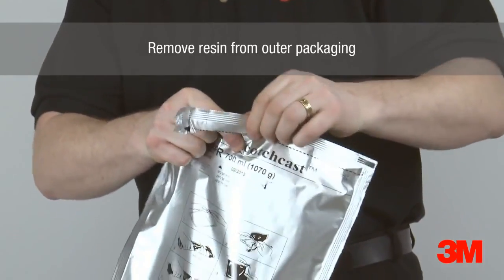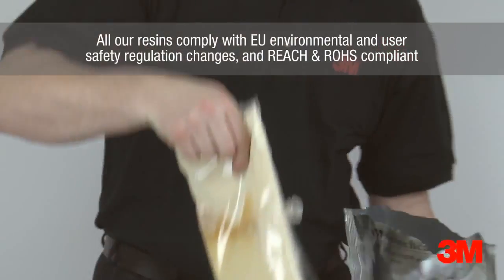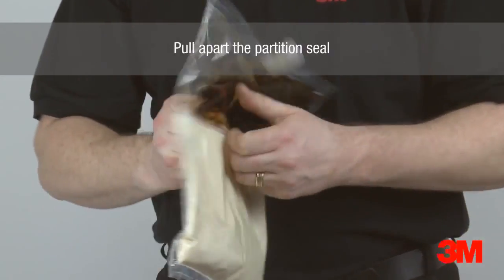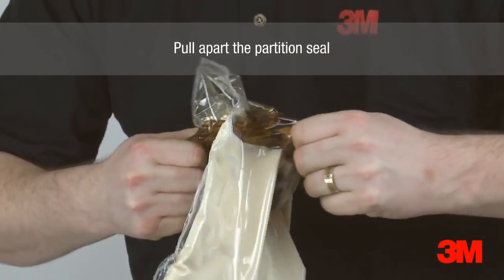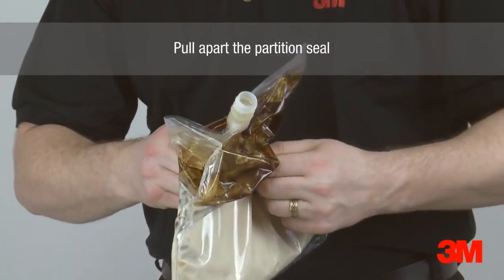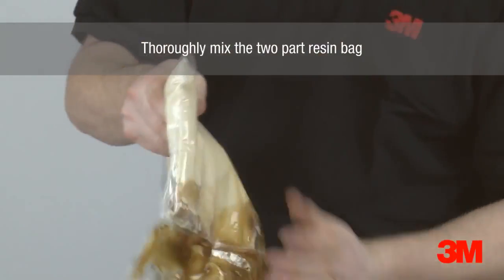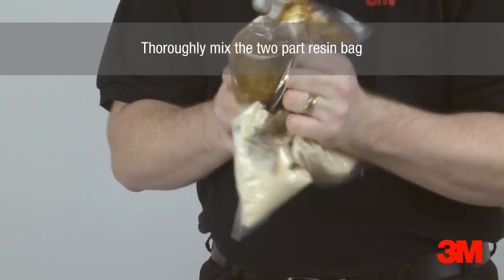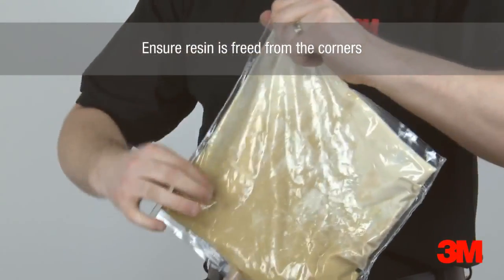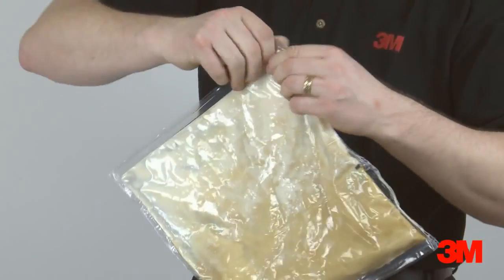We have redeveloped our resin compounds to comply with EU environmental and user safety regulation changes, and are all REACH and RoHS compliant. 3M 1402 FR high quality modified polyurethane resin demonstrates superior performance above all our other resin types. It is for this reason that 1402 FR resin is supplied in the range of 3M hazardous area cable joints covering instrumentation, control cables and power cables rated up to 3.3kV. This resin is also used in hazardous area medium voltage cable joints up to and including 11kV.